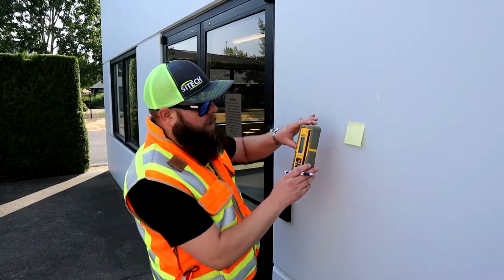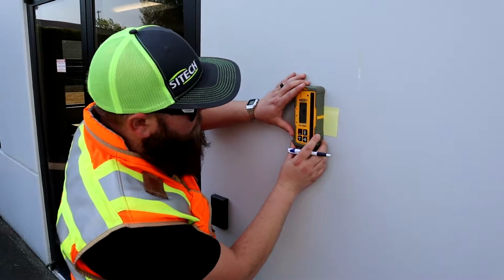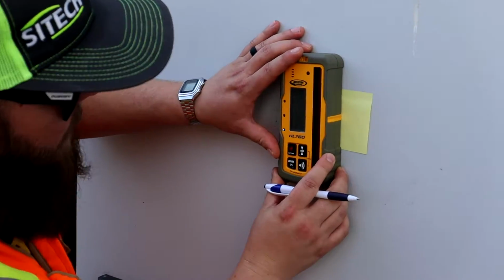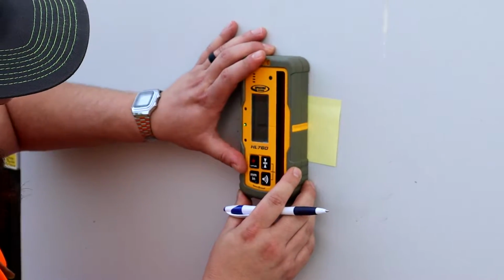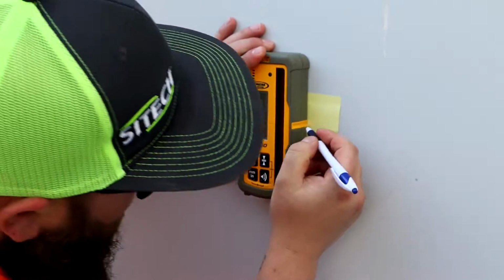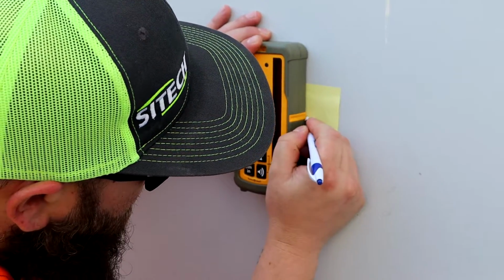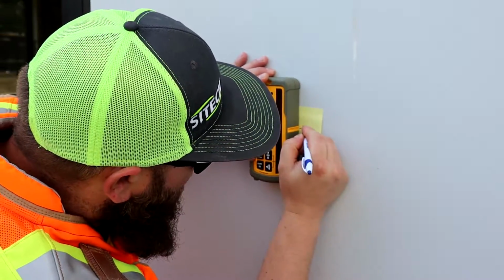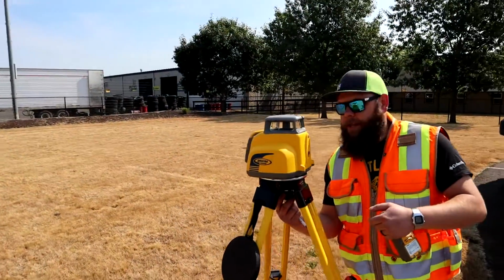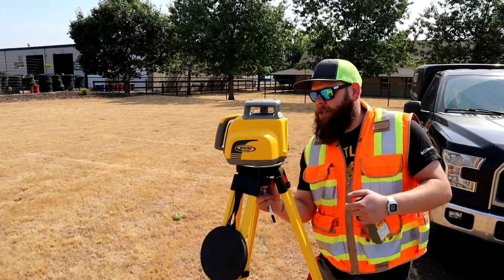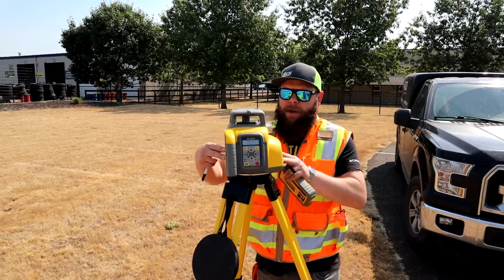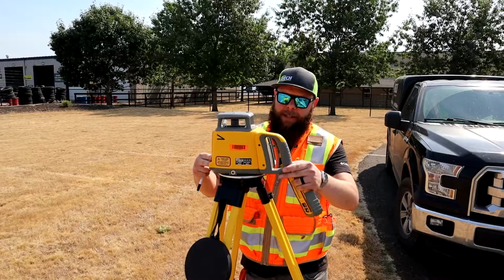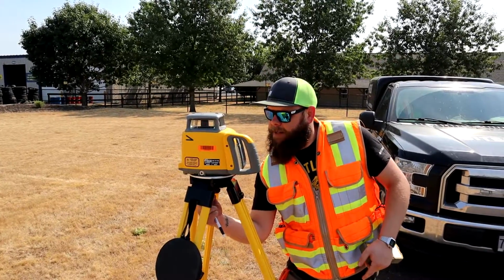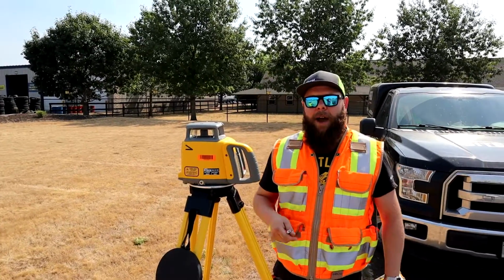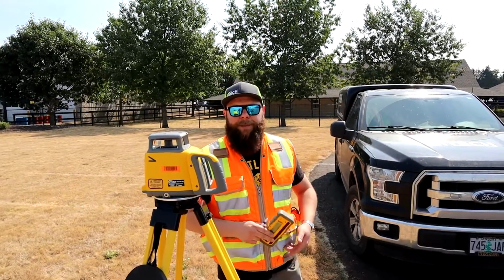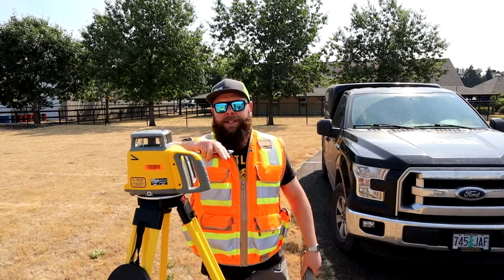So here I am. I'm going to put my receiver on the wall, and I'm going to mark the first side of Y axis. So this would be Y1. I got my tone there. I'll come over here and put my mark and say Y1. So I will gently loosen the 5/8 coarse thread here, and I will rotate it 180 degrees to the other axis, tighten it back down, and we'll wait for it to level back up, and we'll go back to our area and catch the beam and see if there is a difference from one side to the other.